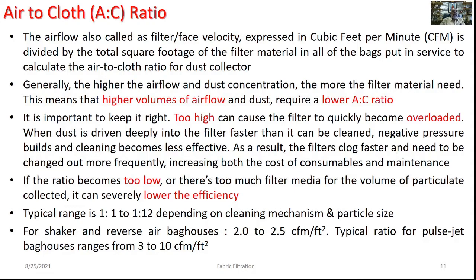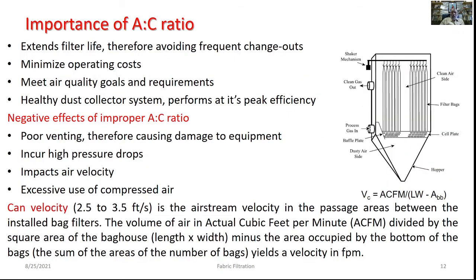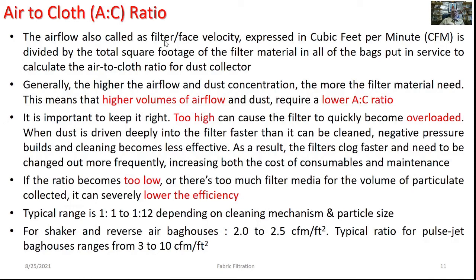The next design parameter is the air-to-cloth ratio. The airflow entering the individual bags is treated as filter face velocity, expressed in cubic feet per minute divided by the total square footage of filter material in all bags in service. Generally, higher airflow and dust concentration require more filter material. Hence for higher volumes of airflow and dust, the air-to-cloth ratio will be less.